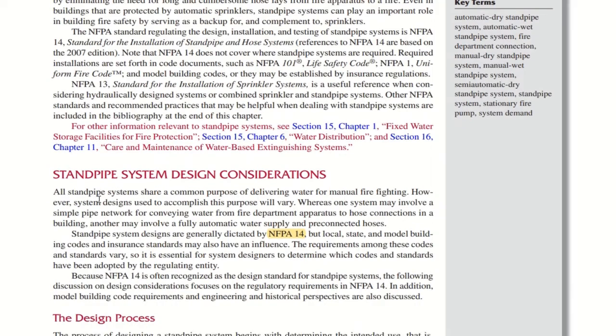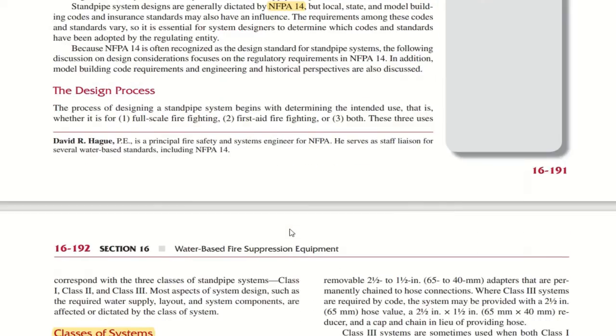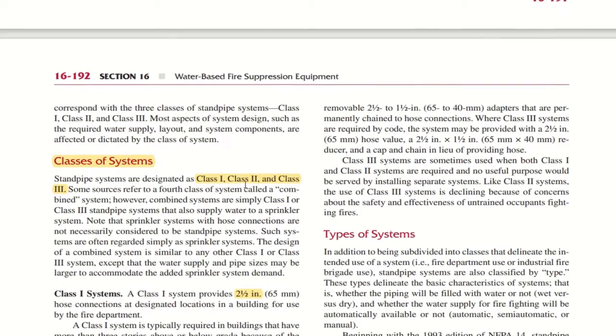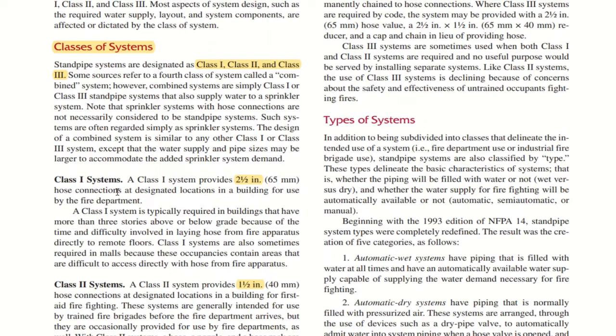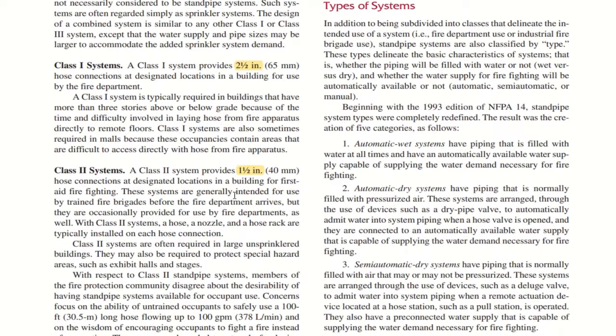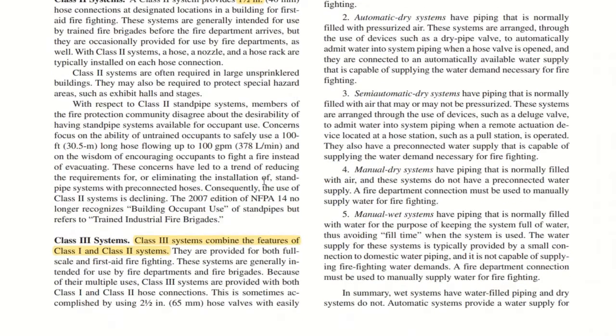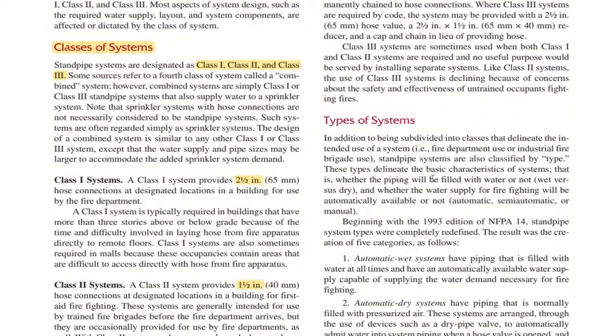Standpipe and hose systems are basically covered in NFPA 14. So, classes of system: there are basically three types of standpipe systems, class 1, class 2 and class 3. Class 1 systems provide 2.5 inch hose connections at designated locations in a building for use by the fire department. Class 2 systems provide 1.5 inch hose connections at designated locations in a building for first aid firefighting. And you have class 3. Class 3 systems combine the features of class 1 and class 2 systems.